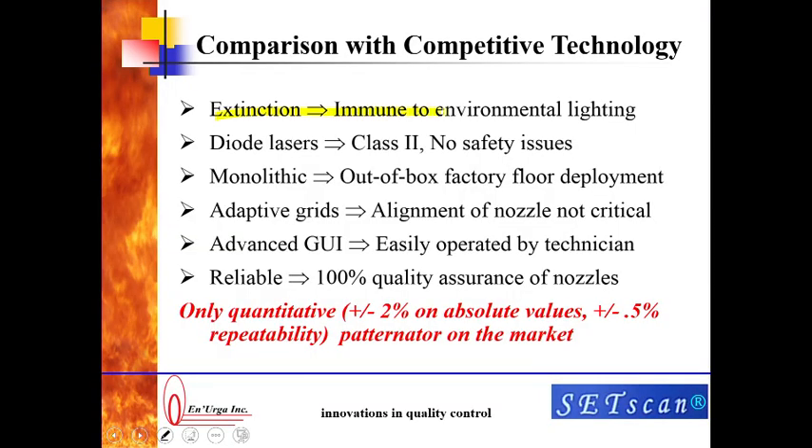The next thing is to compare our method with other competitive technology. We provide surface area density using extinction tomography. Since we are using extinction, it is totally immune to environmental lighting — you can turn on the lights on your factory floor and it will not make any difference to the results. We use Class II diode lasers, so there are absolutely no safety issues. The whole system is monolithic — it is a big chunk of metal, you just take it out and put it on the factory floor and you are ready to go. We use adaptive grids, so it is not very crucial to align the nozzle to the center of the patternator. It has a very advanced user interface and can be easily operated by a technician. It is reliable. This makes it the only quantitative patternator on the market at plus or minus 2 percent on absolute values and plus or minus 0.5 percent on repeatability.